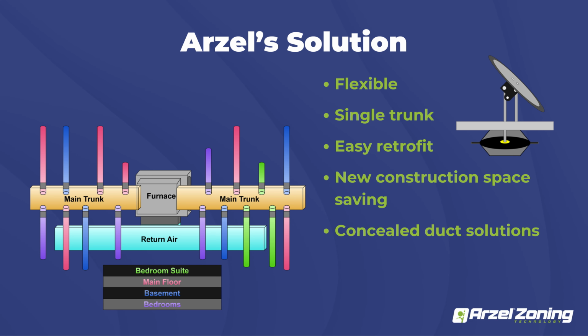That's really what we strive at, just making these jobs as easy as possible for you guys so you don't have to redo ductwork and make that ductwork work for you. You can take that existing ductwork and still be able to zone it and still get those benefits. And really, branch dampers have a little bit more leeway too. Instead of closing off those big sections of your trunk, the branch allows you to have more airflow in your main trunk line because we're closing off the branch side of things rather than the main trunk line. So typically with branch dampers, they have a little bit of a benefit of having a smaller bypass, or possibly not needing a bypass at all, just because of that extra room you have to alleviate some of that extra static pressure in your system as well. So it has some plus sides besides not having to redo the ductwork.